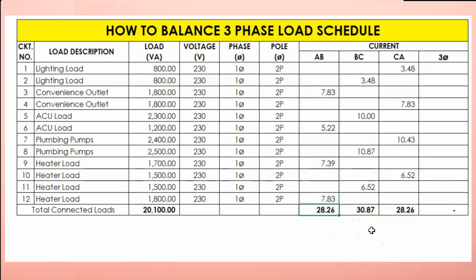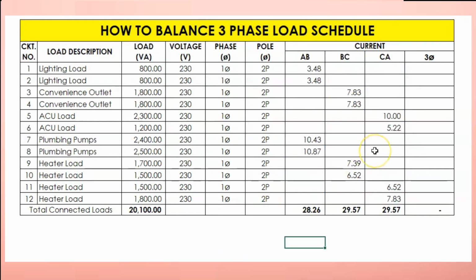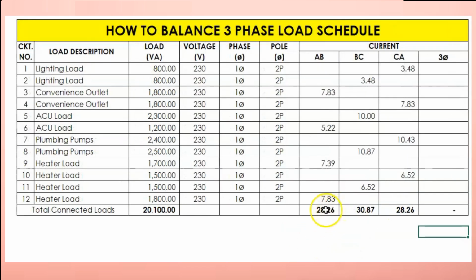They're almost the same as before. Let's start at AB, now at CA again. 28.26, 28.26. If you observe our past load schedule, the totals weren't equal: 28.26, 29.57. Now for us, 28.26. So they're closest to each other. We can conclude that our load schedule is balanced.